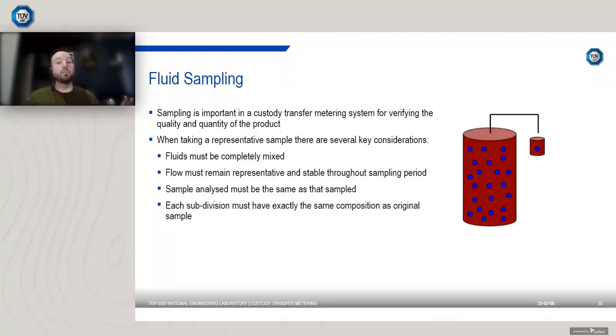A really important point is the sample that you analyze must be the same as that which you've taken from your flow stream. So that's where proper sample handling comes into the fold. So if you take a sample and it's improperly handled, let's say the sample contains volatile components and the sampling container is not suitable, these volatile components can evaporate off, and when it comes to actually analyzing the sample, the composition is changed. And again, when it comes to analysis of a sample, you usually take a smaller subdivision of the sample as a whole. You need to, at all points, make sure that the composition is the same as the original sample.